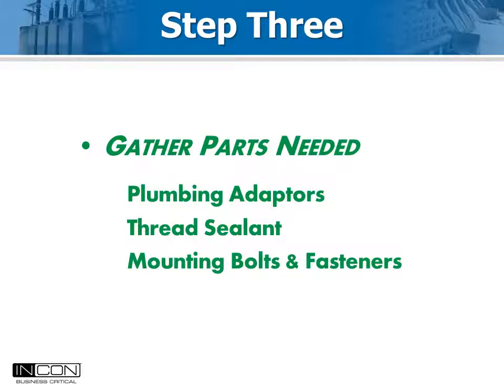The third step is to decide how you will connect the gas density sensor to the plumbing of the breaker. The sensor is always a 3/8" British standard parallel pipe thread. The sensor may be installed at the fill port, as you will see. It may be installed as part of a gas piping update, or a T-fitting may be installed in the existing gas piping.